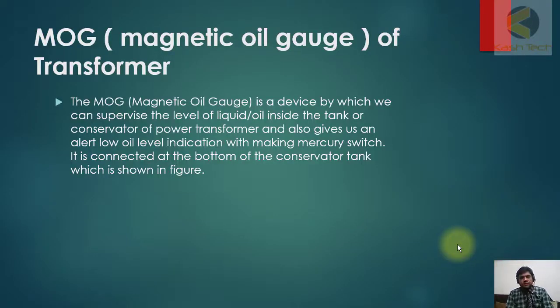Welcome guys, let's move up to the next topic: MOG, Magnetic Oil Gauge of transformer. On the conservator tank, the oil gauge indicator is available and you will see how it's working. The magnetic oil gauge is a device by which we can supervise the oil level of liquid or oil inside the tank or conservator of power transformer, and also gives us an alert low oil level indication with making mercury switch. It is connected at the bottom of conservator tank which is shown in figure.